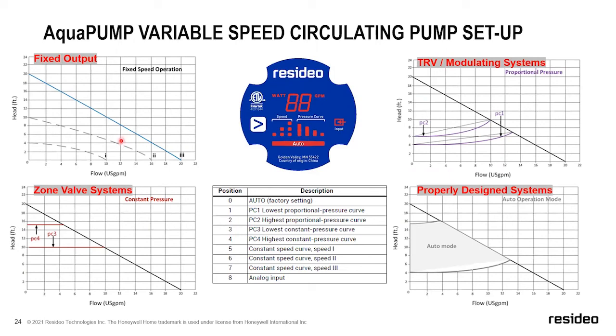And then we also have the capability of running a fixed speed operation. So think of this like a basic pump. We have been operating 3-speed circulators for a long time. The way those work is it's almost 3 pump curves in one circulator. So you buy a pump, you slap it on, you set it to the curve you need, and you walk away. That's basically what you're doing with these 3 different speeds right here. You basically have an ECM motor that's running off a fixed speed output. So it's no different than putting one of our old 3 speeds on, but getting a little bit more efficiency out of it. That's all that does.